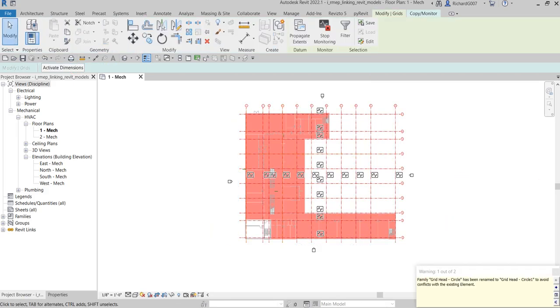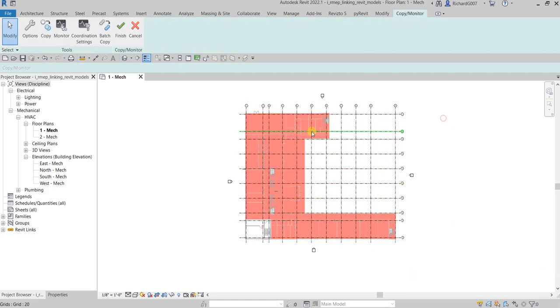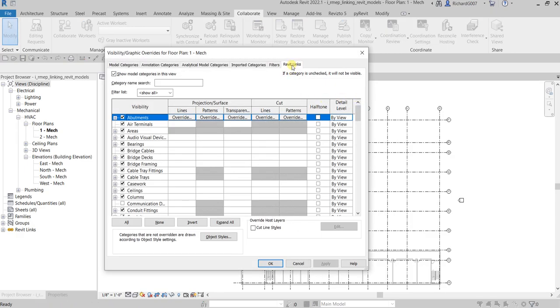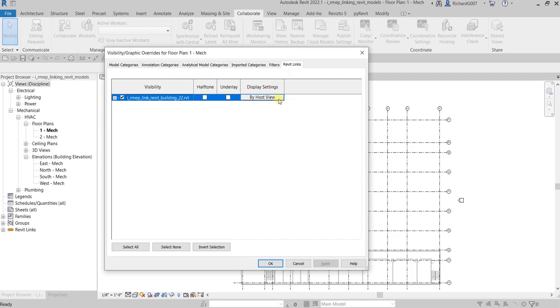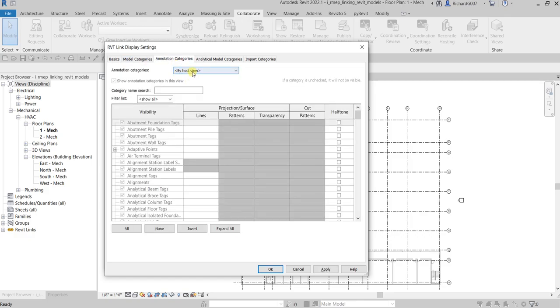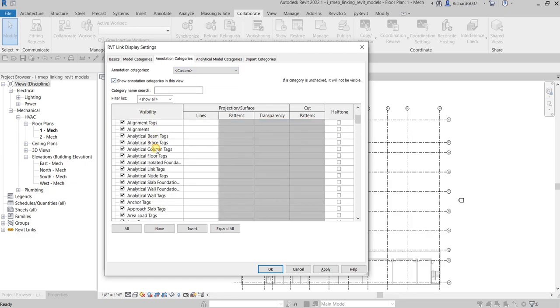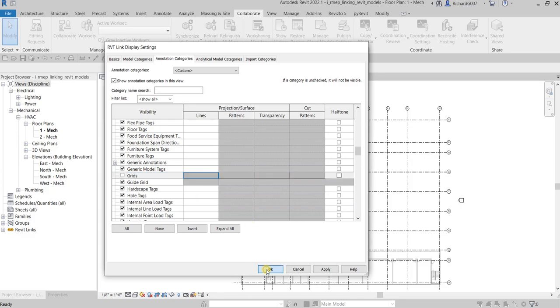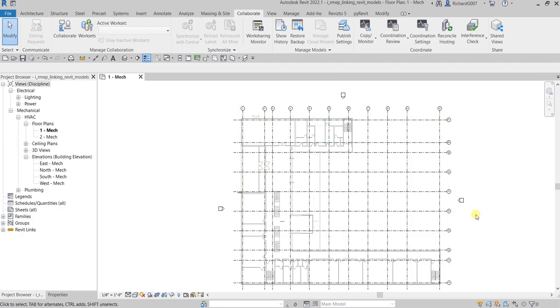It's now copied. After copying the grids from the architectural model, I hide the architectural grids. To do that, go to Visibility/Graphic Overrides, go to Revit Links, find the link model, go to Display Settings, make sure it's Custom. Go to Annotation Categories, make sure this is Custom, and then uncheck Grids to hide them from the link model so you only see MEP grids.